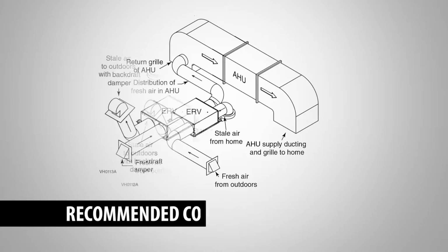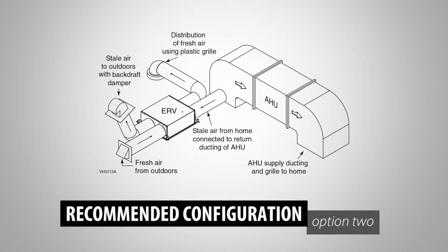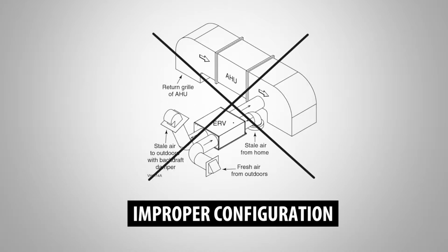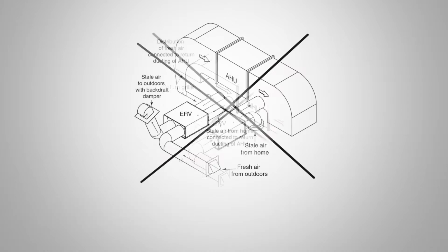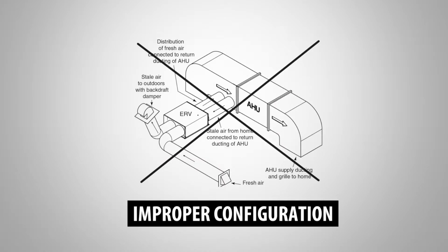The second configuration with the AHU draws stale air from the return ducting of the AHU and distributes fresh air into the living space through registers. Do not connect the system with fresh air from the ERV going into the distribution ducting of the AHU, which can result in condensation issues during cooling season. Do not connect both distribution of fresh air from the ERV and stale air exhaust in the AHU return ducting.